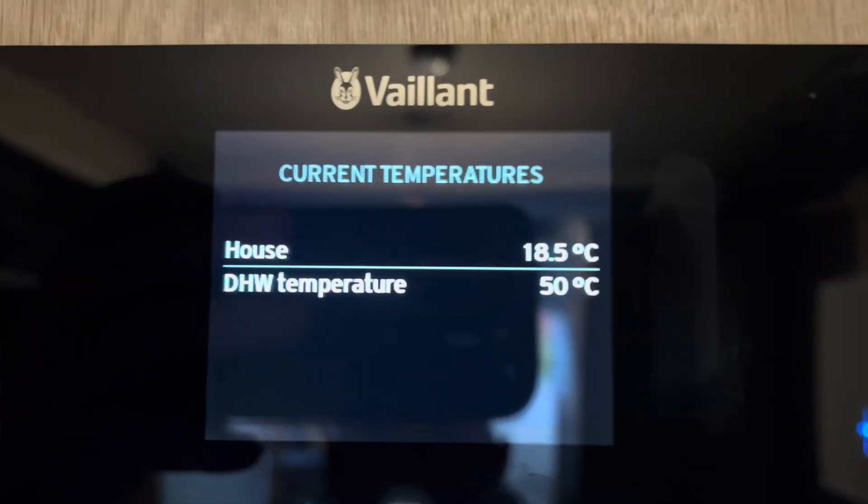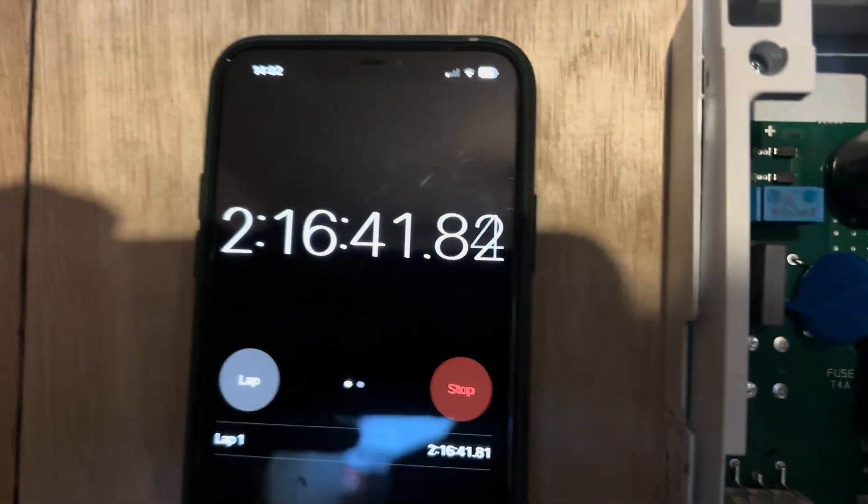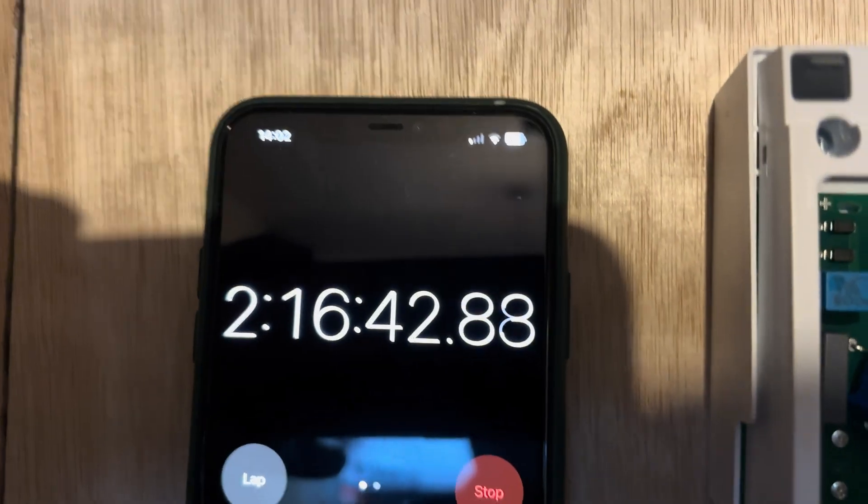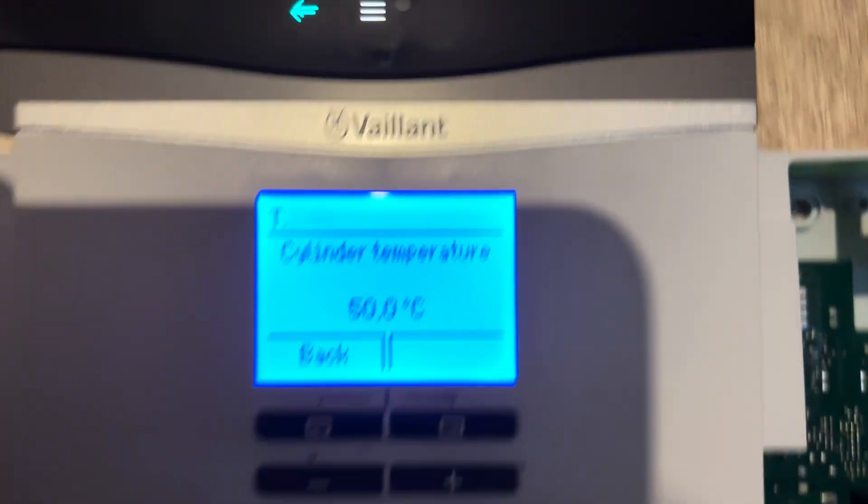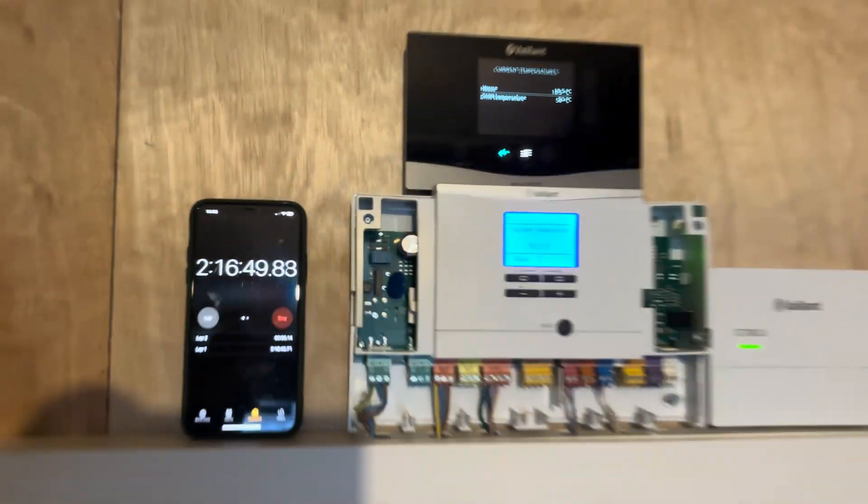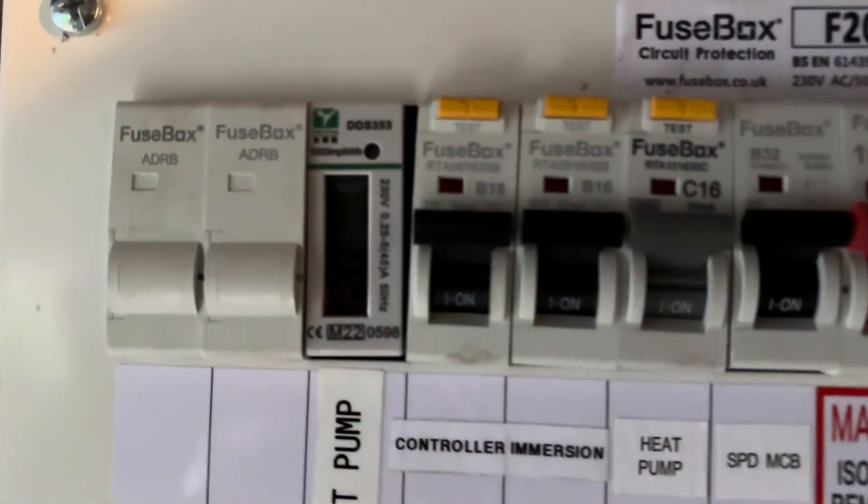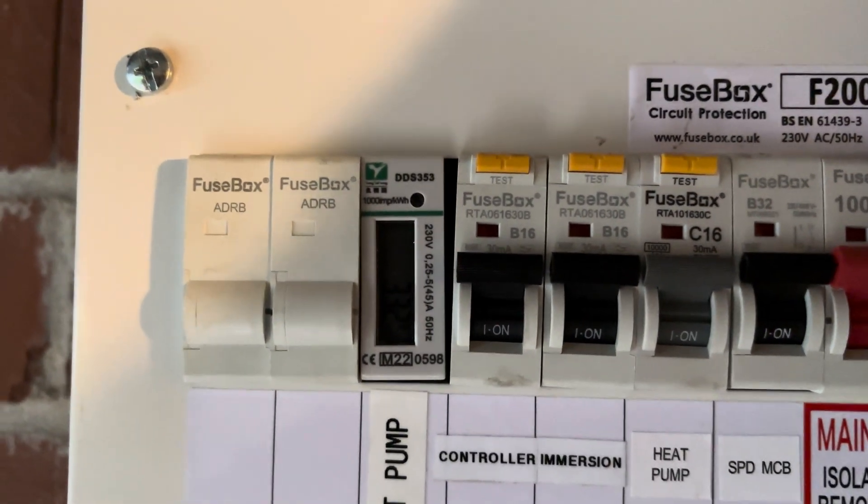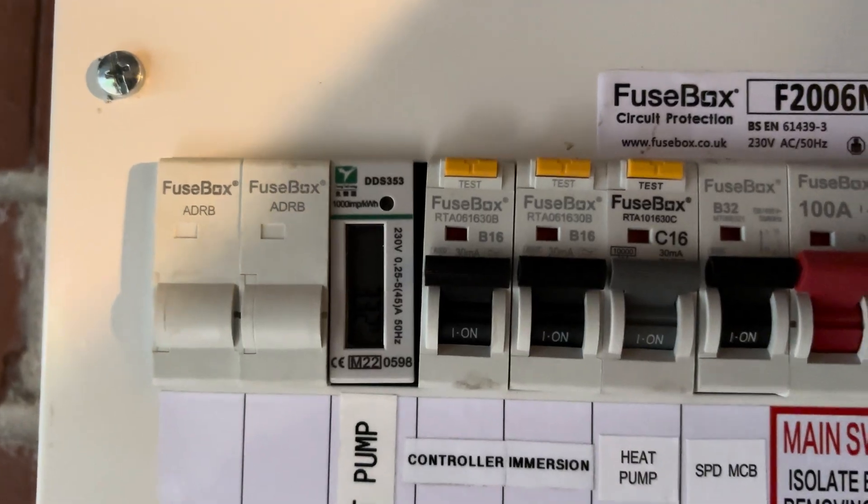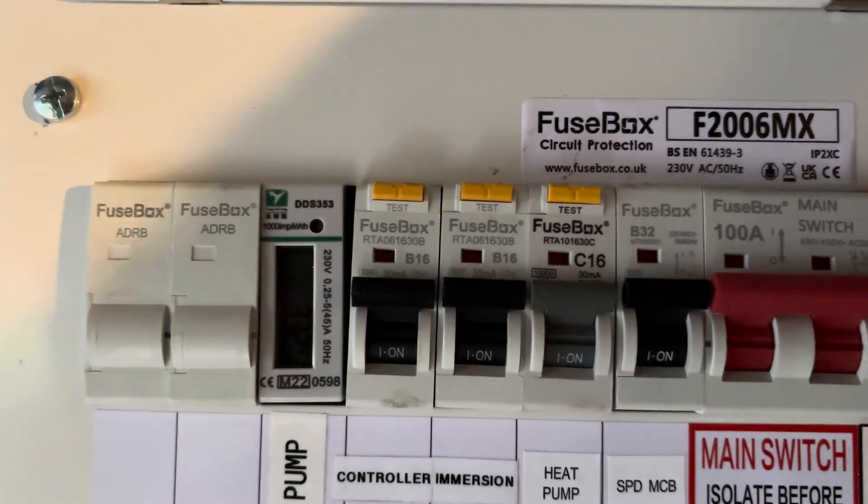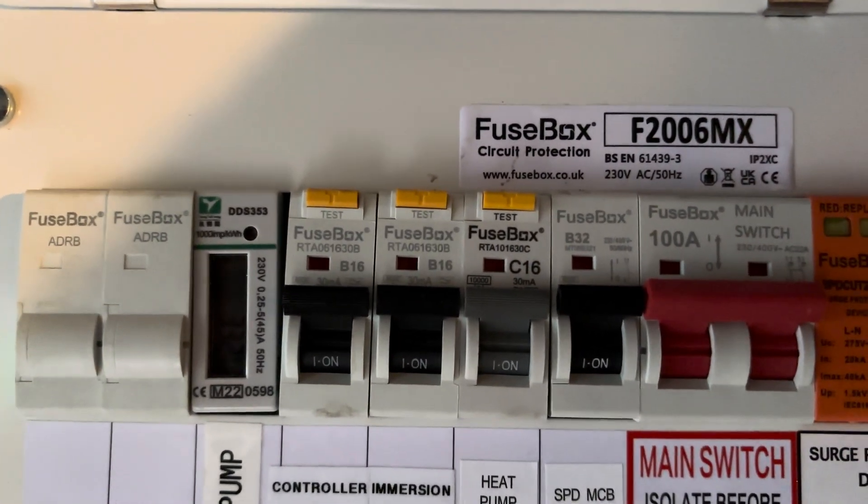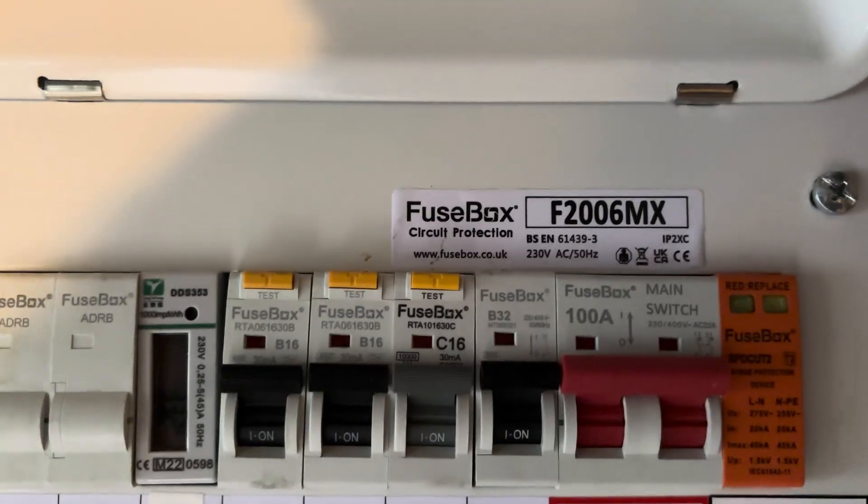Okay, we've just hit 50 degrees C now. That's 2 hours 16 minutes to get from 11 degrees C to 50. Let's see how much electric we've used. We've used 3.32 kilowatt hours of electricity to heat the hot water from 11 degrees C to 50 degrees C.